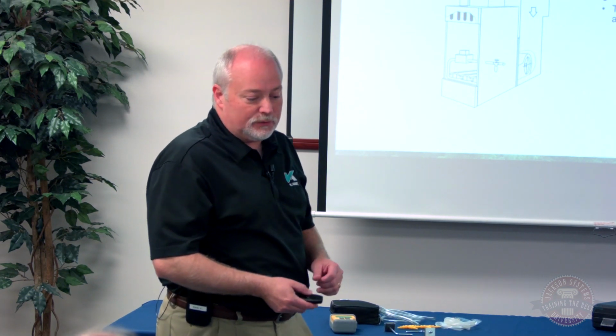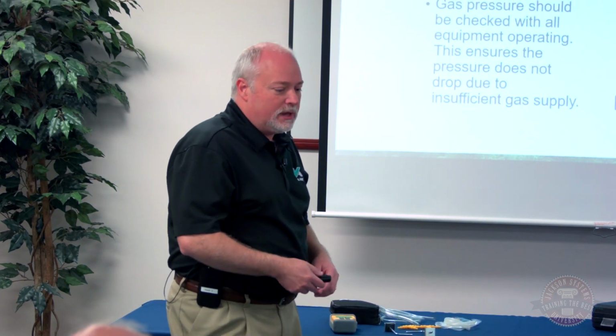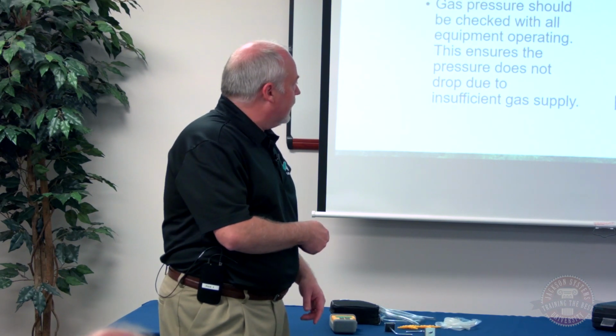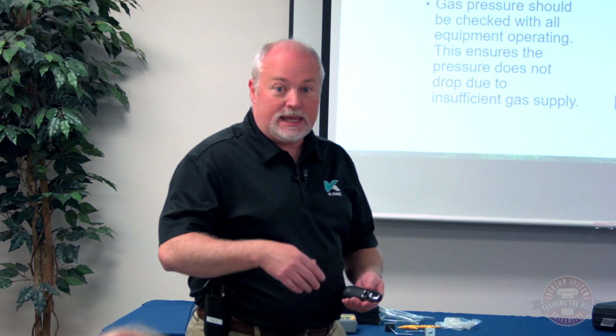Then moving on to one other thing I should mention here too. Anytime that we're checking gas pressure, we want to do that when the equipment is operating. Okay, we don't want to have the equipment off and check our pressure. We want to make sure and fire that appliance. And if there's other equipment, other parts of the building on that same gas line, that should be on also.